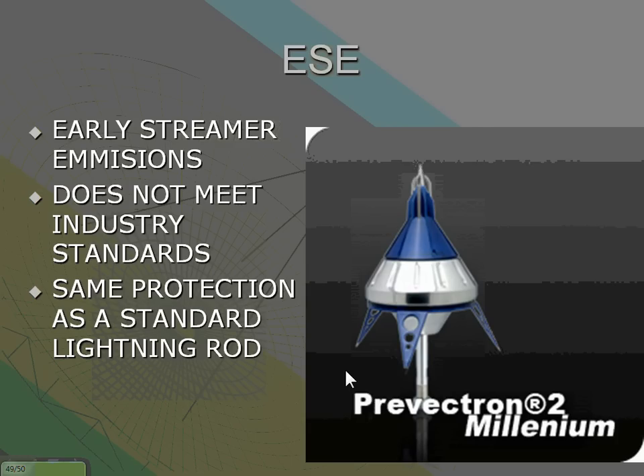The last thing I want to touch on is what's called an ESE system - an early streamer emission. It's not part of the industry standard. A lot of people selling these tell buyers, I can put this one lightning rod on your roof and it will protect the entire thing, which is actually a false statement. A lot of engineers do get hooked into buying these things. A standard lightning protection system has terminals every 20 feet on the outside and every 50 feet in the middle. Unfortunately, one of these single rods won't protect the whole roof, even though it would be cheaper and easier if it did. So these aren't UL listed - none of LPI, UL, or NFPA will certify them. They've done extensive tests on whether they work, and they've just failed everything.